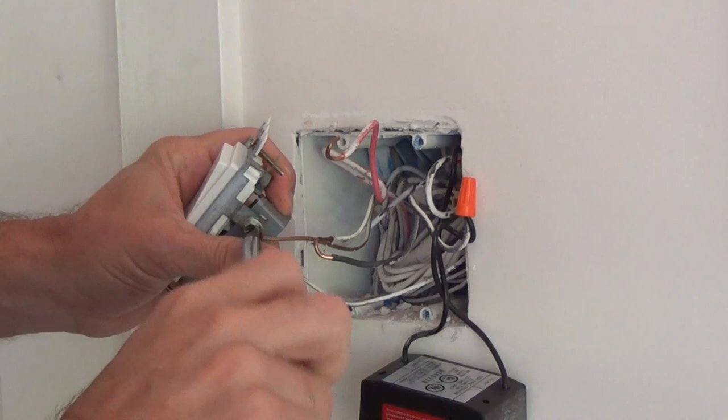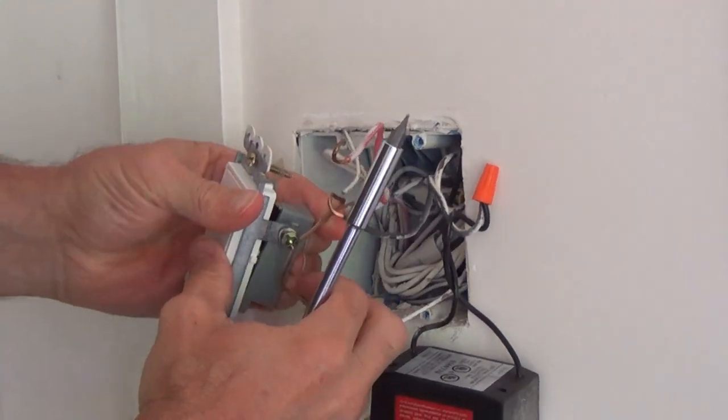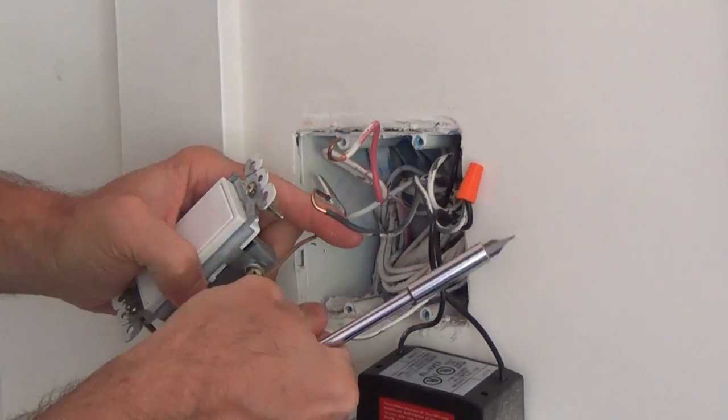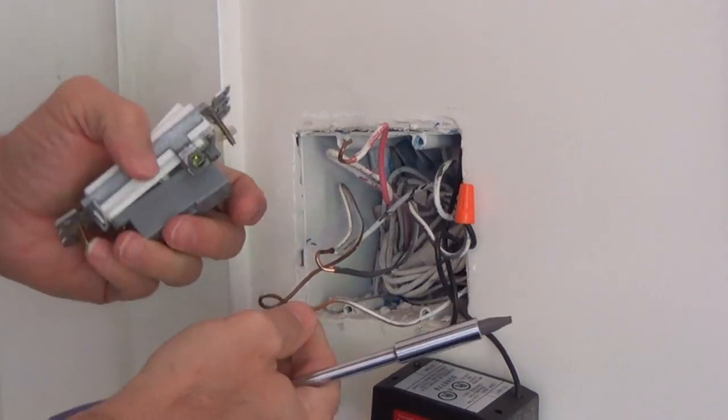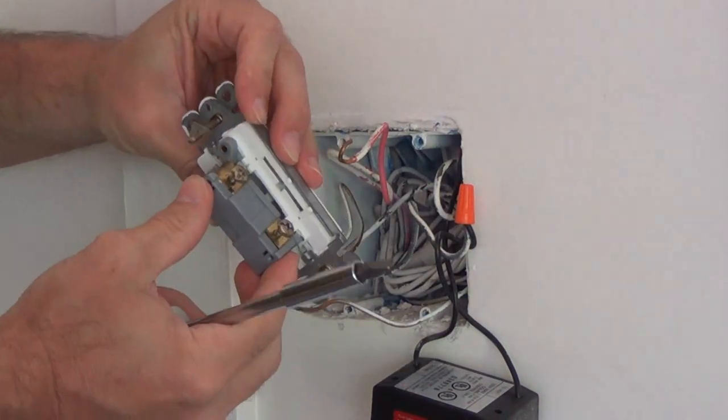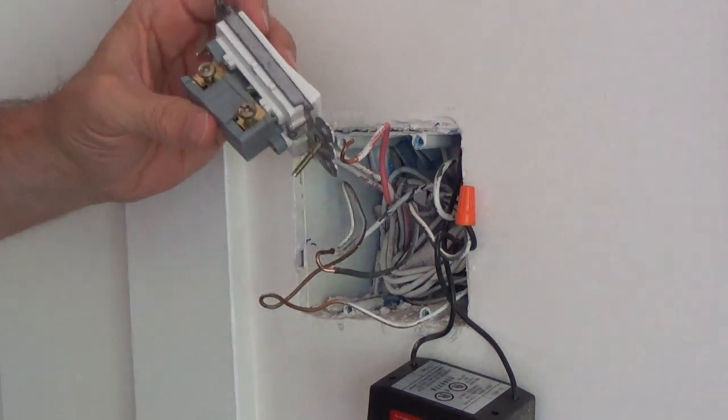And then turn this around and remove the grounding wire. Open it up. And you can see the problem here. It's actually a broken case, and that's what was causing the short. I'm going to replace it with a brand new one.